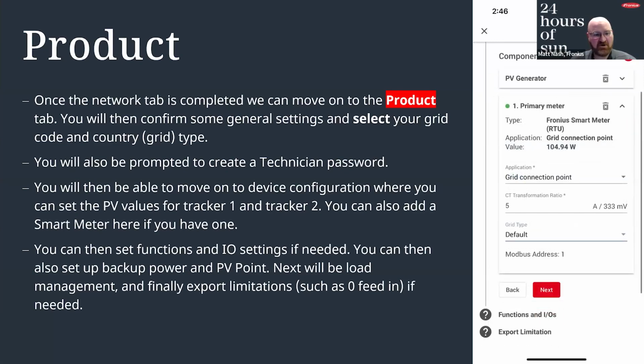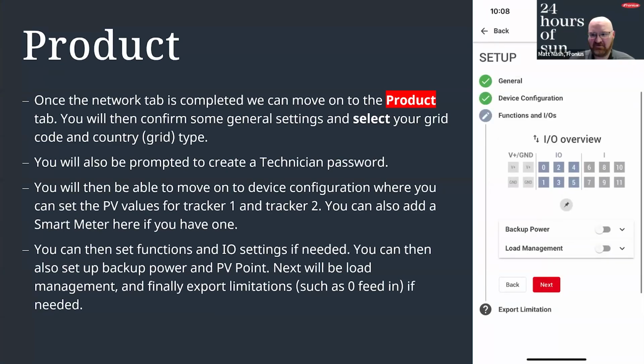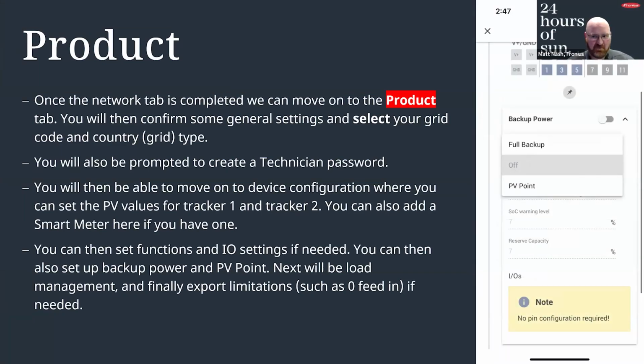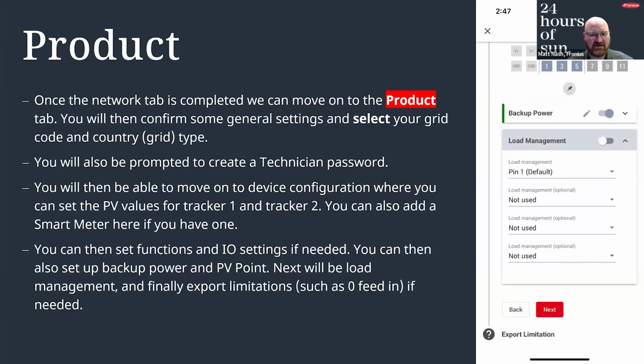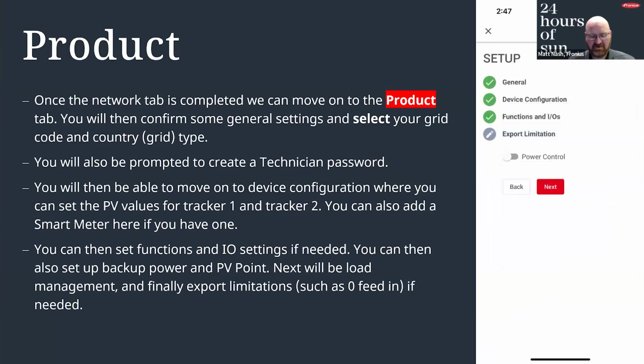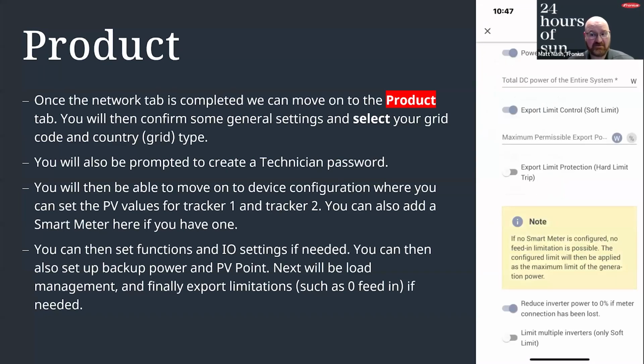Next, this is where you would set up a smart meter if you had it. Also, you can set up a battery if it's already connected. And then you can adjust settings for the digital I/O ports. You can select which type of backup power that you want to do, whether it be the PV point and the full backup. You have to have one or the other. You can't have both at the same time. And then this is where you would select what pins do what for specific loads. You can also set up an export limitation at this point. So you can effectively limit it to a certain wattage output, or you can actually do a 0 feed-in with these settings.